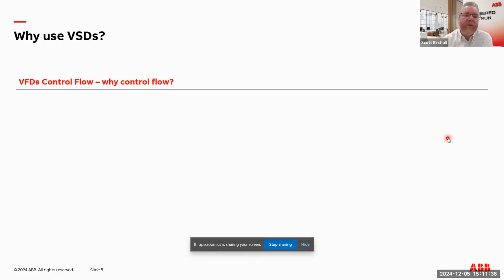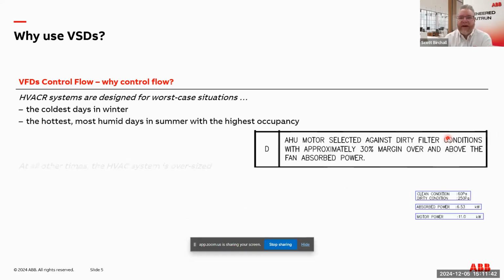So why do we want to use VFDs? One of the reasons is flow control. We look at our HVAC systems. They're designed for the coldest days in the winter. I got up this morning and it's minus 10 C here in Wisconsin, and the wind chill is going to make it a lot worse. I waved to my boys at the corner waiting for the bus, all sitting there looking like icicles. But we have to design the system for days that are a lot colder than today, for those coldest days.